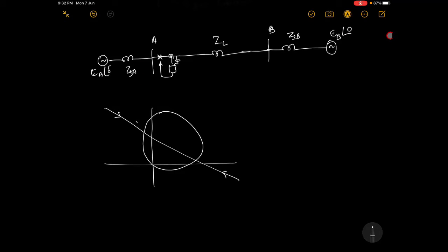When there is a power swing, it means an outage of a big tie line or a large load, so power variations will be large. We call it a power swing, and this is the locus of power swing, correct? And this is our load characteristic, suppose. This is our trip region and this is our restraint region. This is actually a circle.